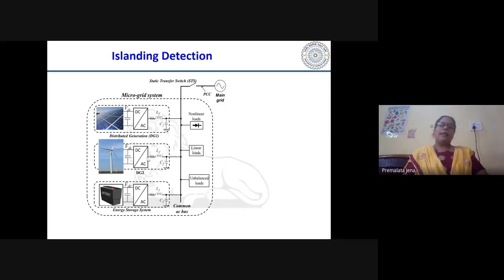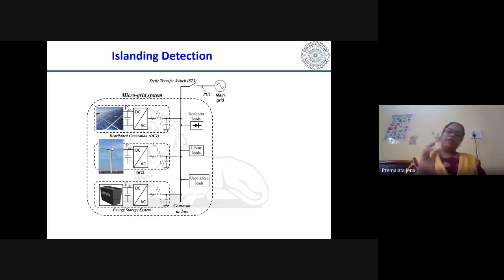So this unintentional islanding creates voltage and frequency variation. Why? Because when the main grid is off, due to this power imbalance, the generation is less and the load demand is more. So there is a mismatch between load and generation. Therefore, delta P and delta Q will basically be the governing factors now. Delta P controls the voltage and delta Q governs the frequency. In the distribution network, in the low voltage network at 230 volt cable level, the resistance is dominating in nature. So therefore P controls V and Q controls the frequency. But this concept is just the opposite in transmission. So this 20-30% of renewables may or may not supply the loads.